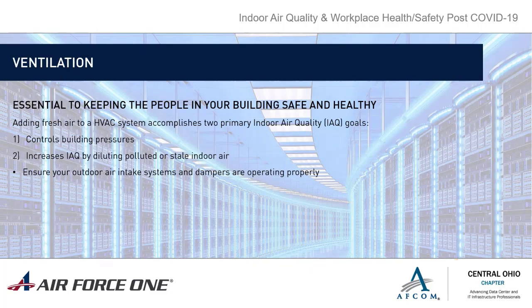Yeah, thanks Austin. Of course, more airflow and air change in your space is always good, but sometimes that comes with a cost, and that cost is energy use and the amount of work your equipment has to do. As you increase outdoor air, you have to put more heat into it to reheat it during wintertime, and use more tonnage of cooling during the summertime. So it puts a heavier burden on your equipment and on the kWs you use for energy.